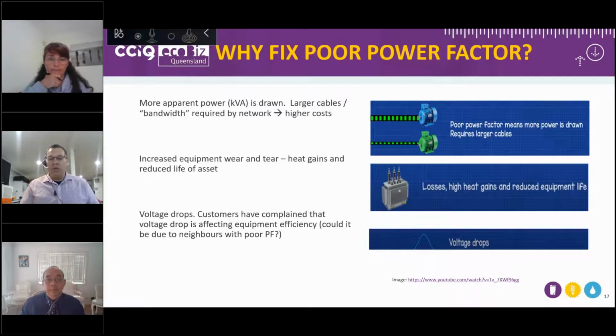The second reason is that poor power factor can increase wear and tear on equipment through the heat gains and losses as things are turned on and off within a premises. So the life of your equipment can be shortened, and therefore you have greater costs because they're not running to maximum life. And then voltage drops. Having poor power factor on site can not only affect your site equipment, but it can also affect the local network as well. So you may be doing damage to your equipment on site, but you can also potentially be contributing to damage to equipment at your neighbour's site as well. So these are the key reasons why we would like to see poor power factor attended to.